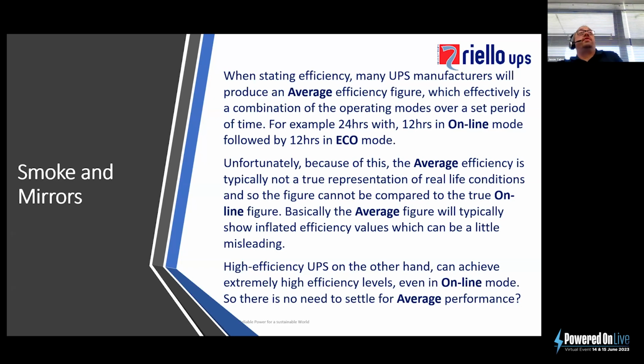So basically, the average figure will typically show an inflated efficiency value, which can be a little bit misleading when you're trying to work out a total cost of ownership, i.e. the energy you're going to be saving long term. So what we can say here is that high efficiency UPS systems, on the other hand, can effectively achieve extremely high levels of efficiency, even in online mode. So there is no need to settle for average performance.